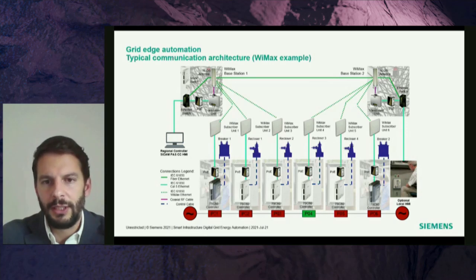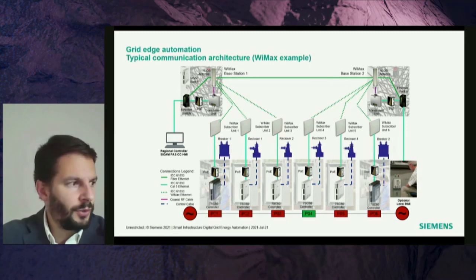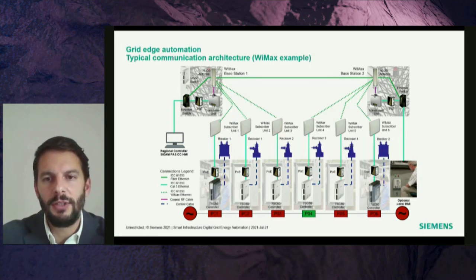This slide represents a typical installation on a loop network. The single line diagram at the bottom shows two substation sources on a loop feeder with an open tie, a normally open point. In this example, the grid edge automation employs the state-of-the-art communication standard in the electrical world that we just saw, IEC 61850, for all operational and non-operational data exchange among these devices. In the diagram, the communication media is supported by WiMAX radios, as you can see in the picture.